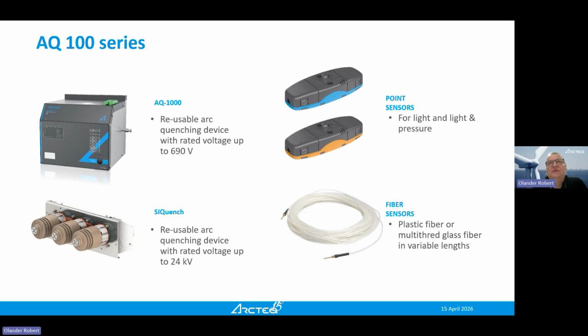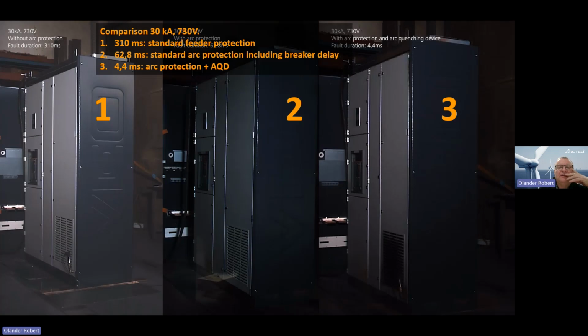Typically, these quenching devices are one-time use. So if it operates, you need to change to a new one. And that means, of course, you cannot test it, because if you operate it, you will need to change to a new one, which is not tested. So there we are quite unique, and that's why we are also doing quite well on the arc protection. So here you see now, this is a video representation. This is a test we did in Berlin with switchgear of one of our partners.